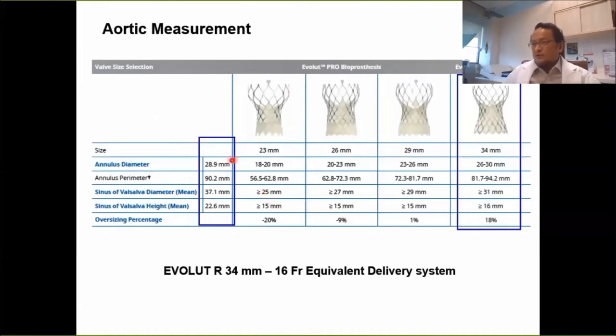So this is the patient's own assessment, and from here we can calculate the perimeter. And that perimeter falls into a valve which is a 34 mm valve. So that's what we're going to choose. The 34 mm valve has a 16 French equivalent delivery system.